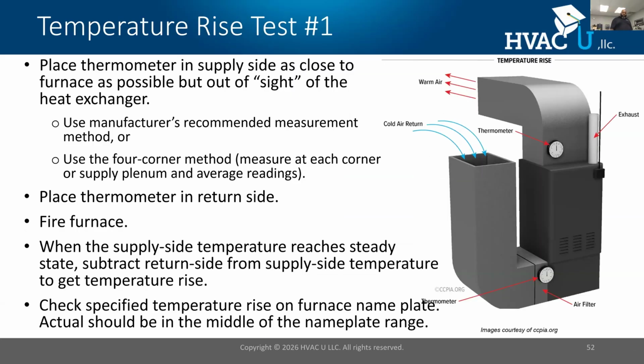What about temperature rise? Temperature rise is oftentimes unutilized. When I'm dealing with a combustion appliance, it has a rating plate that specifies the range that the temperatures are supposed to be, supply and return. As an auditor or a technician, we can measure the supply and return, see what the difference between those two numbers is, and make a comparison. This lets us know: am I circulating enough air through that furnace and duct system? And that's a temperature rise test.